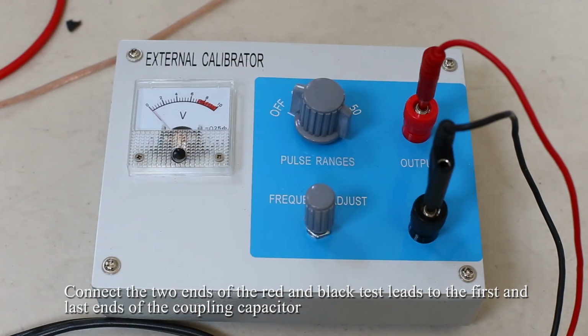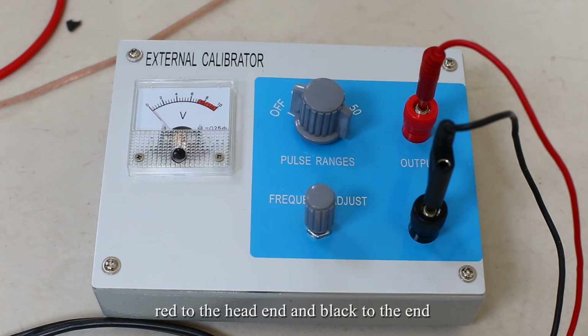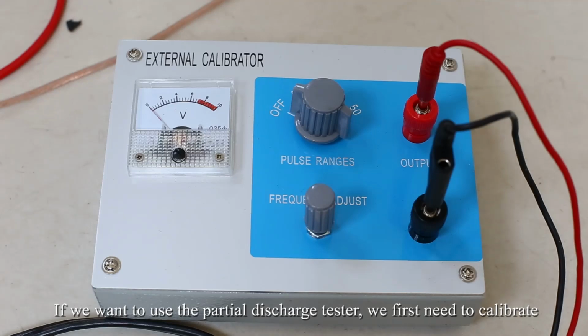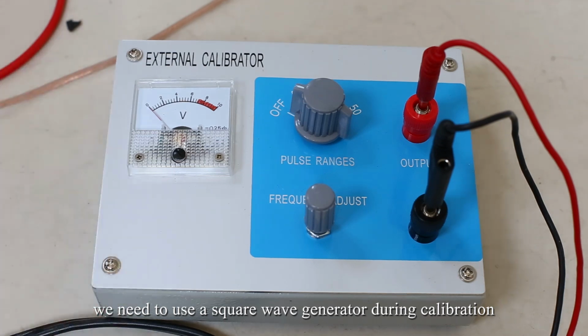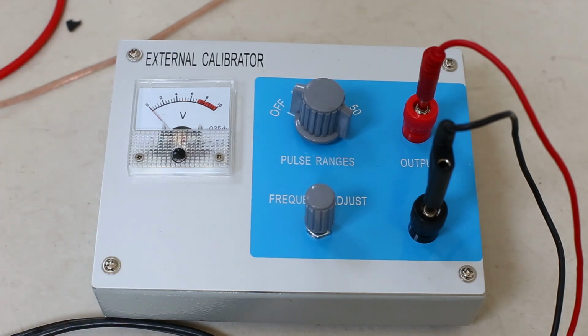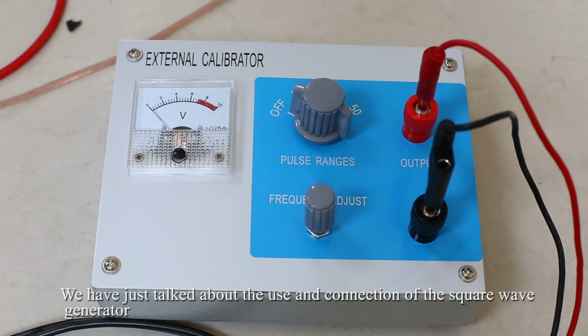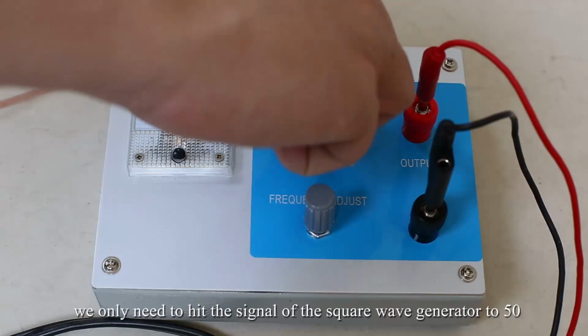Connect the two ends of red and black test leads to the first and last end of the coupling capacitor, red to the head end and black to the tail end. If we want to use the partial discharge tester, we first need to calibrate, we need to use a square wave generator during calibration. We have just talked about the use and connection of the square wave generator. We only need to hit the signal of the square wave generator to 50.